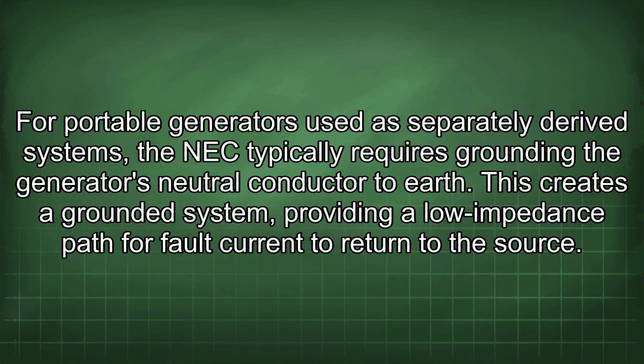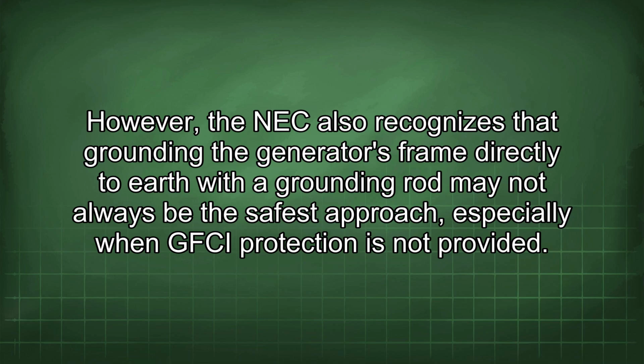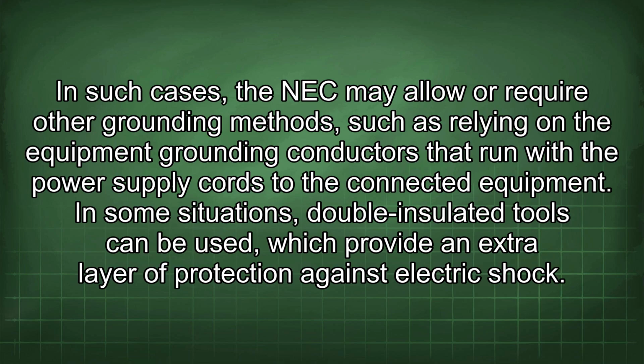For portable generators used as separately derived systems, the NEC typically requires grounding the generator's neutral conductor to earth. This creates a grounded system, providing a low impedance path for fault current to return to the source. However, the NEC also recognizes that grounding the generator's frame directly to earth with a grounding rod may not always be the safest approach, especially when GFCI protection is not provided. In such cases, the NEC may allow or require other grounding methods, such as relying on the equipment grounding conductors that run with the power supply cords to the connected equipment.